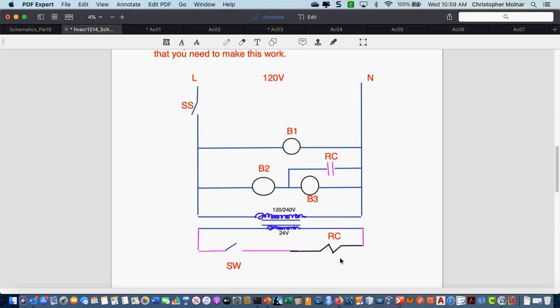Now, I have several people in the class, and again, I'm not going to name names on a call. It wouldn't be right. I value your privacy too much for that. But several people in the class are turning in schematics that make me think you might have an electrician background. Some of the schematics you're turning in show more what an electrician would draw for wiring diagrams. When we're talking ladder schematics, I need a schematic that has the outside rails, which will be the line or neutral, or on the low voltage side, my power and my common, and the loads and the switching devices go across on rungs between the rails.